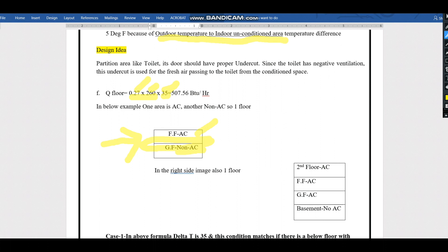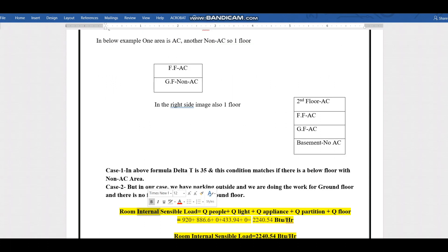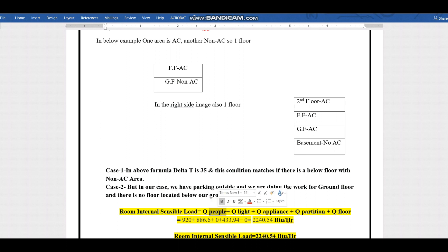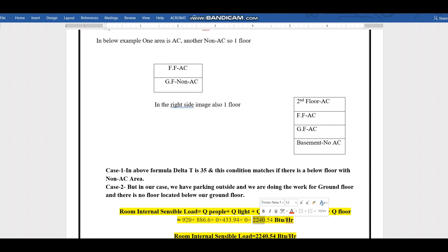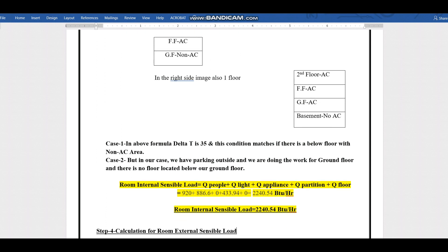The total room internal sensible load equals: Q people load (sensible only), Q light load, Q appliance load (shown for example only), Q partition load — 433.94 — and Q floor load (zero in our case). The total comes to 2240.54 BTU/hr. We still have room external sensible load, external-to-internal load, and latent load remaining to determine total airflow, total cooling load, and off-coil temperatures.